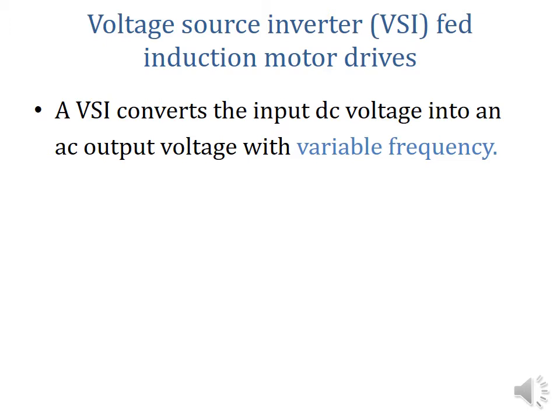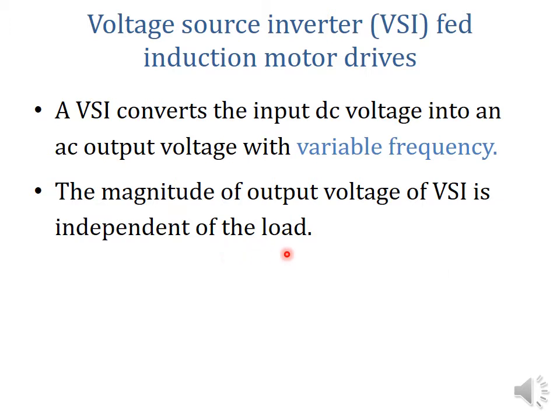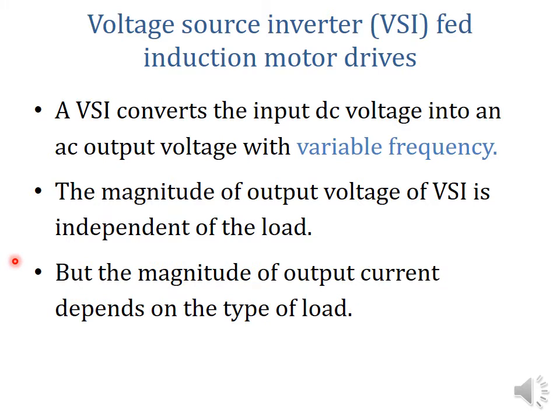A VSI, or voltage source inverter, converts the input DC voltage into an AC output voltage with variable frequency. That means the VSI provides a variable frequency output voltage that can be used to control the speed of an induction motor. The magnitude of the output voltage of the VSI is independent of load, while the magnitude of the output current depends on the type of load.